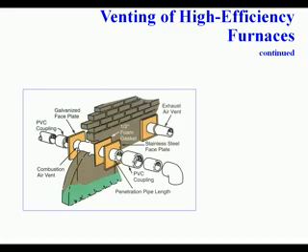When venting a furnace horizontally, manufacturer procedures must be followed. Vent pipe should follow the shortest route with the fewest elbows. Intake and exhaust exiting a sidewall must be as accurate as possible. A drain line is necessary for disposal of condensate. Furnaces must be individually vented and not combined with other appliances. PVC connections must be tight and must not leak.